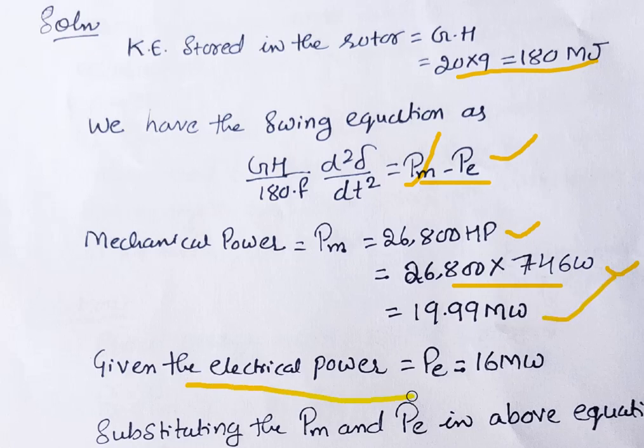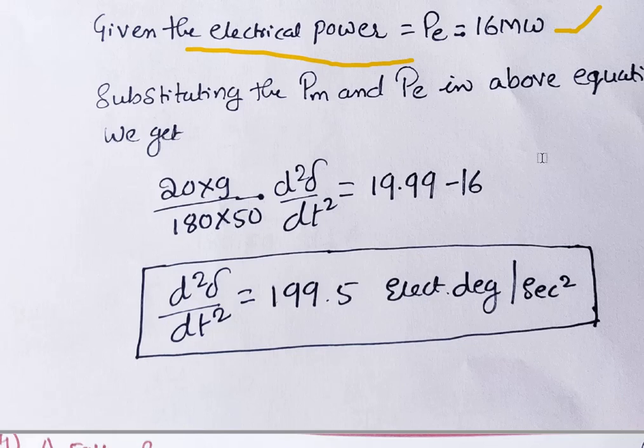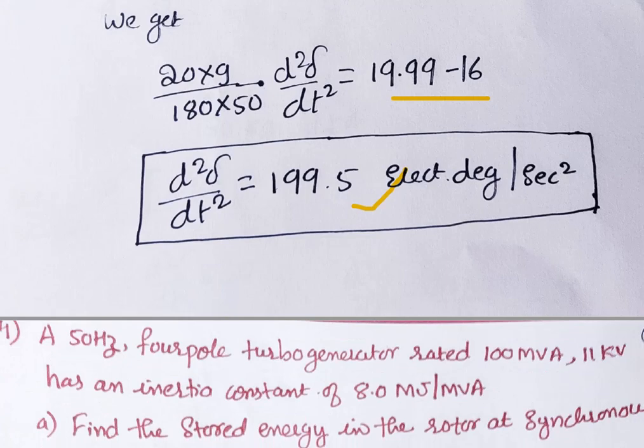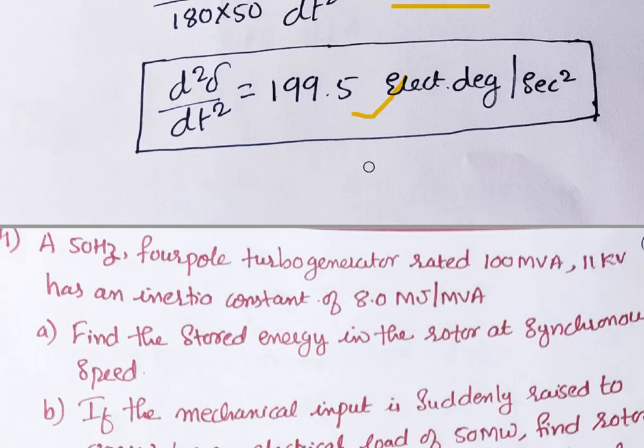Substituting P_M = 19.99 MW and P_E = 16 MW into the swing equation with G·H = 180 and f = 50 Hz, we solve for d²δ/dt² and get the acceleration = 199.5 electrical degrees per second squared. This is the final answer for problem three.